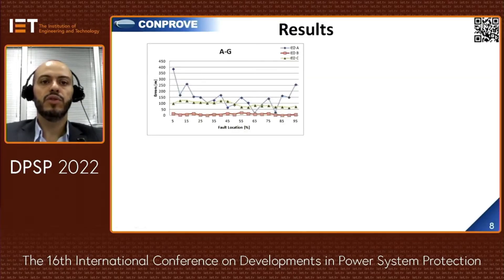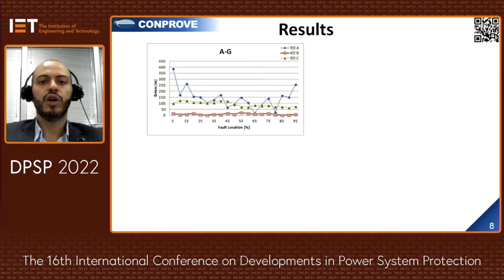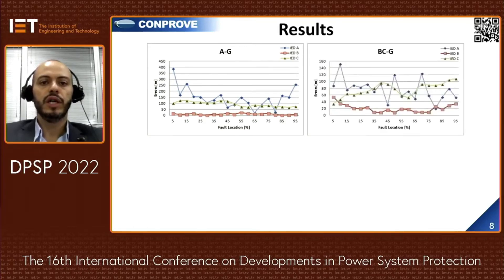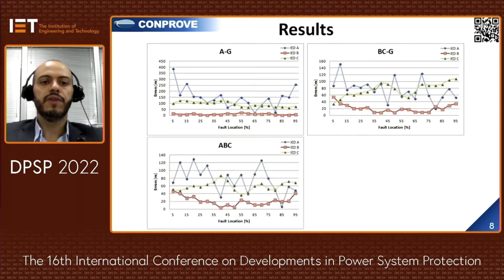The test results of the three IEDs are shown. In the graphic, the horizontal axis shows fault location in percentage with a 5% step, and the vertical axis shows the error in meters. The AG ground fault results are shown in blue for IED A, red for IED B, and green for IED C. Results are also shown for a BCG ground fault and for a three-phase fault across all three IEDs.